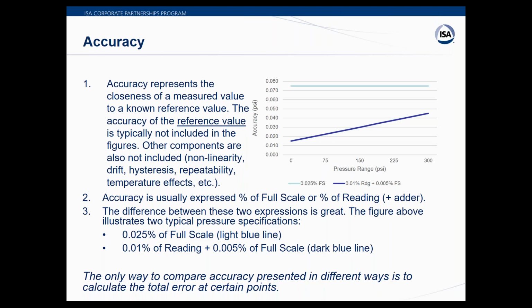So on this slide, let's talk about accuracy. Everybody focuses on accuracy. When I make a presentation to a client, they want to know how accurate is your calibrator? And when we're testing an instrument, how accurate is the transmitter? How accurate is the sensor? So on and so forth. Just as a definition, accuracy represents the closeness of a measured value to a known reference value.